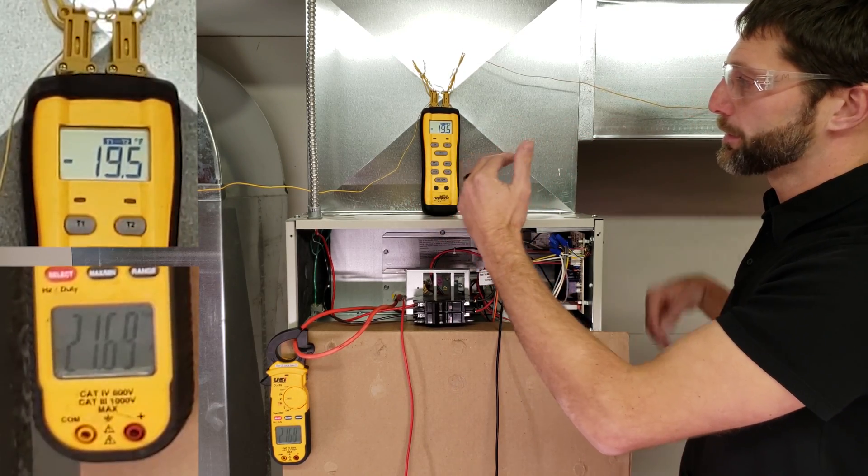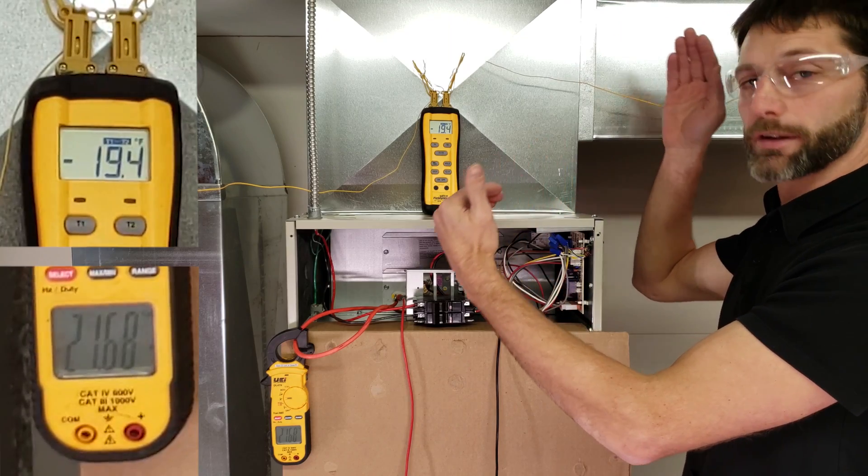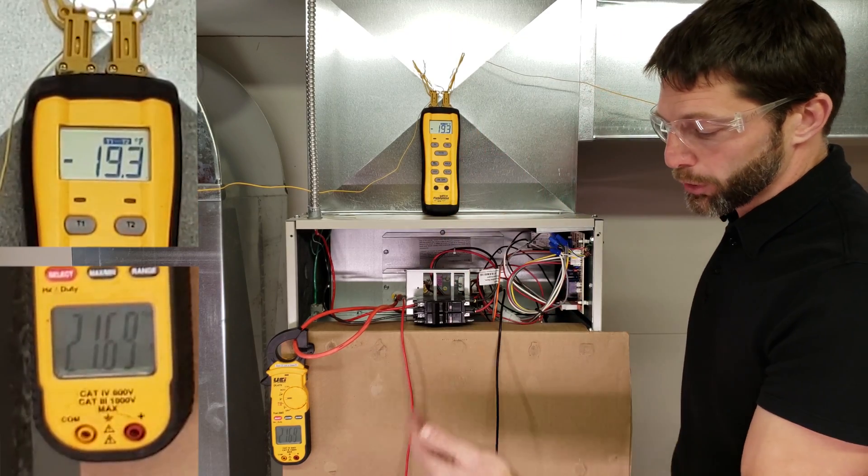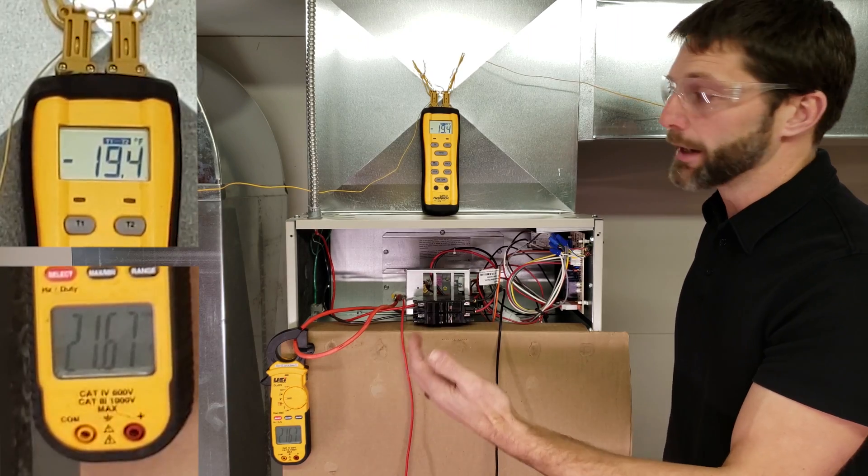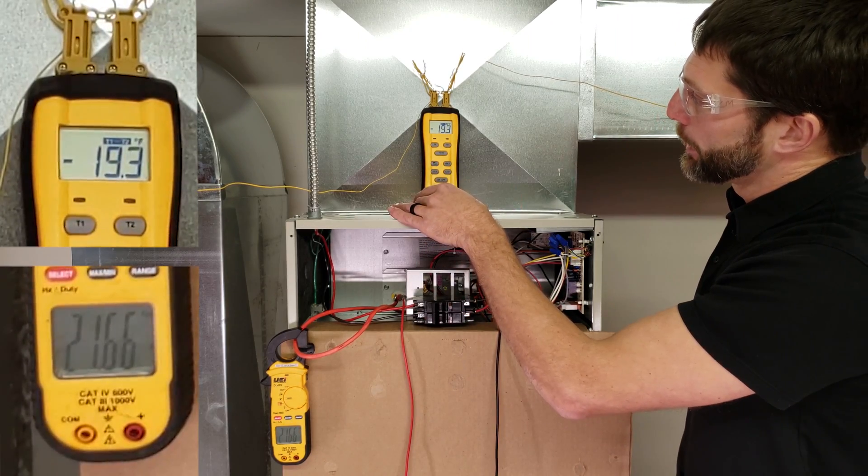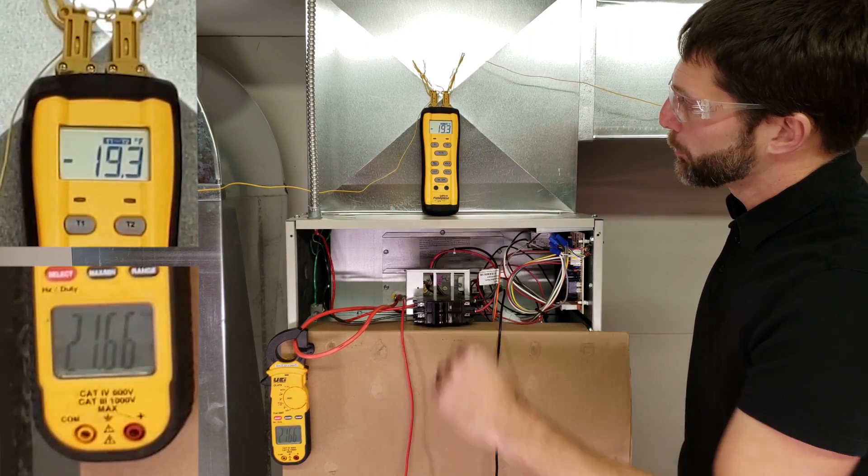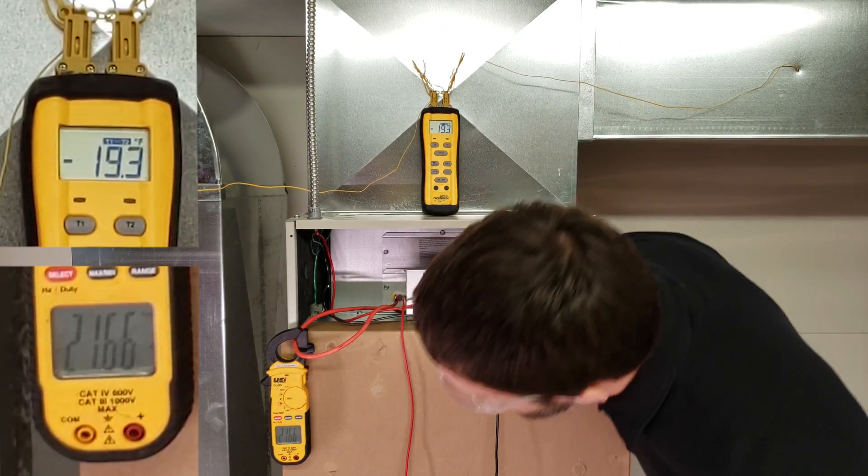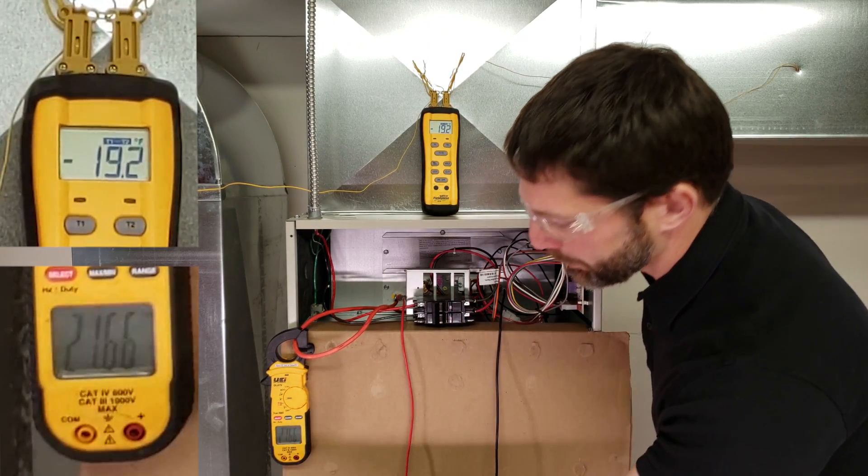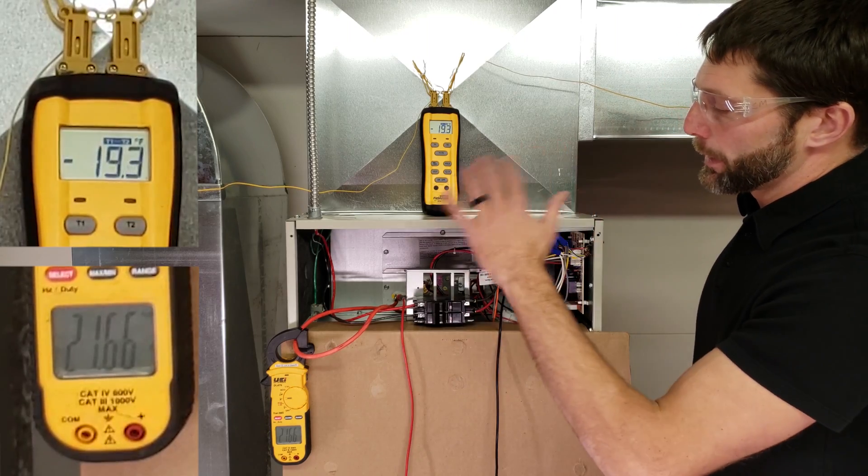But the thing is, what we want to keep in mind is if that temperature differential keeps rising, then that means that our blower motor speed is not high enough, or we have an airflow restriction or something like that. So right now we're reading right about 19.3 degrees as a temperature differential, and 21.65. So that's what we got right there.